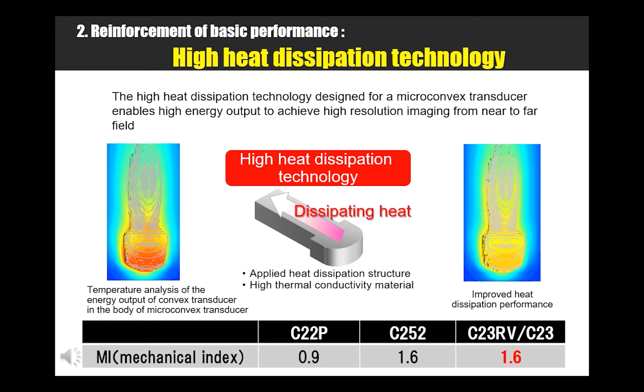The new microconvex probe has improved its heat dissipation capability by reviewing the heat dissipation design and can output nearly twice the sound pressure of a conventional type, or the same as that of a normal convex. This has enabled us to obtain strong harmonic signals to the depths and maintain high resolution from near to far field, which was difficult with a conventional microconvex. The cable is light and easy to handle, and the shape is very comfortable to hold.